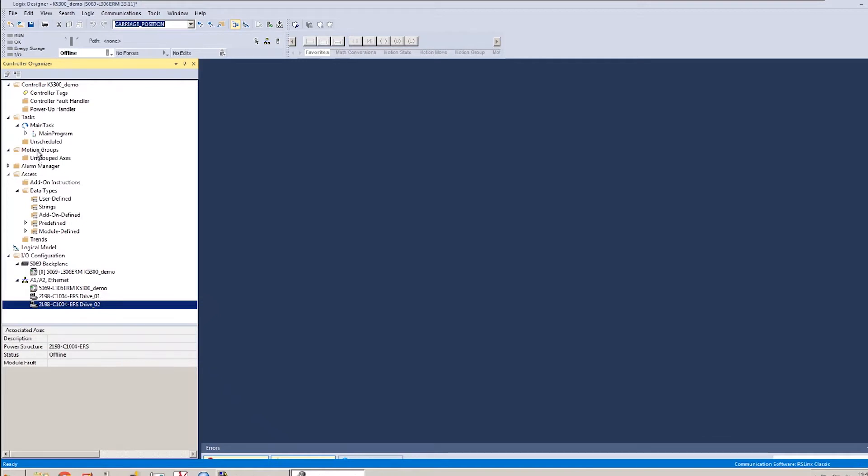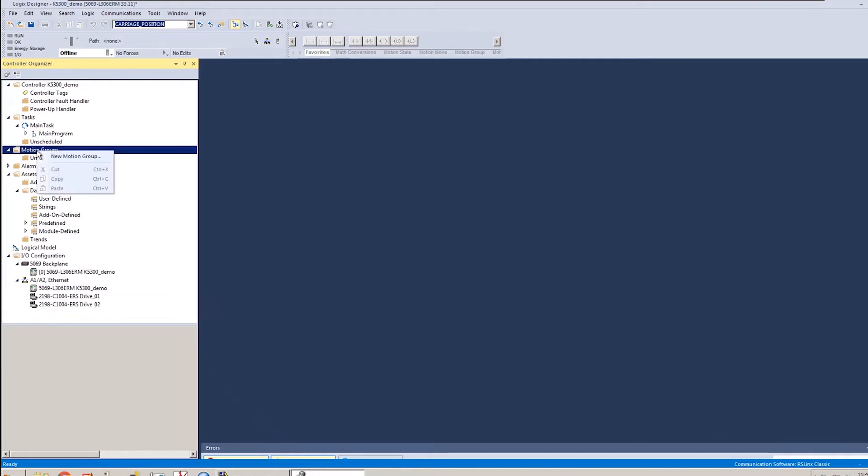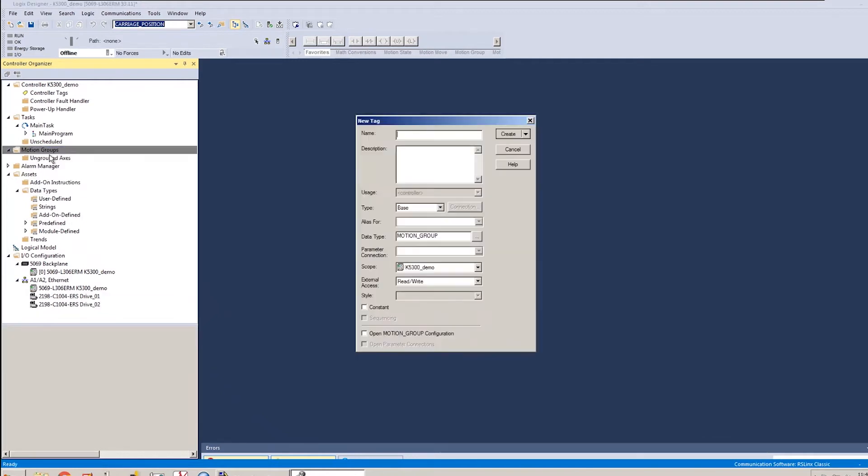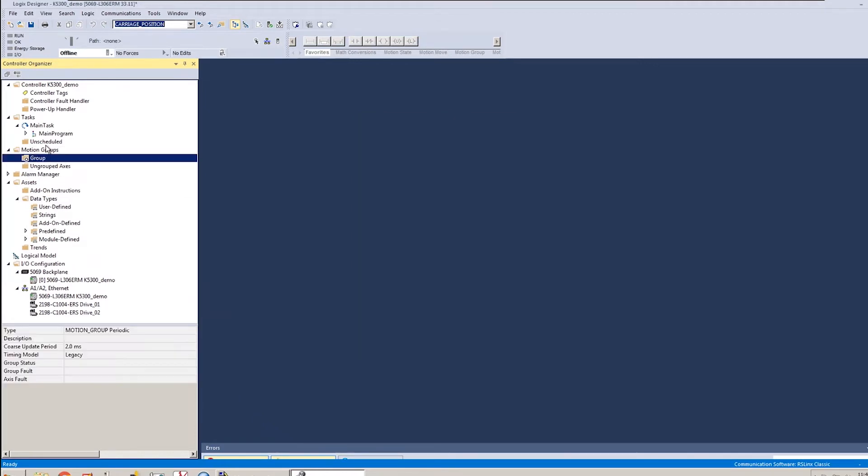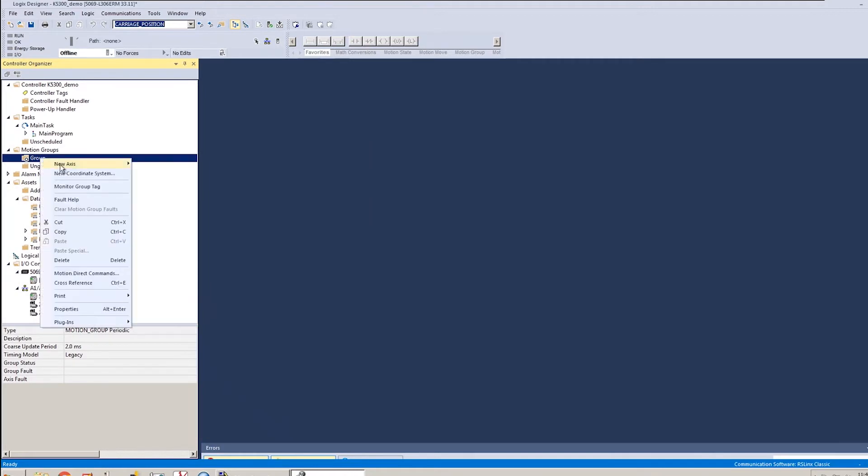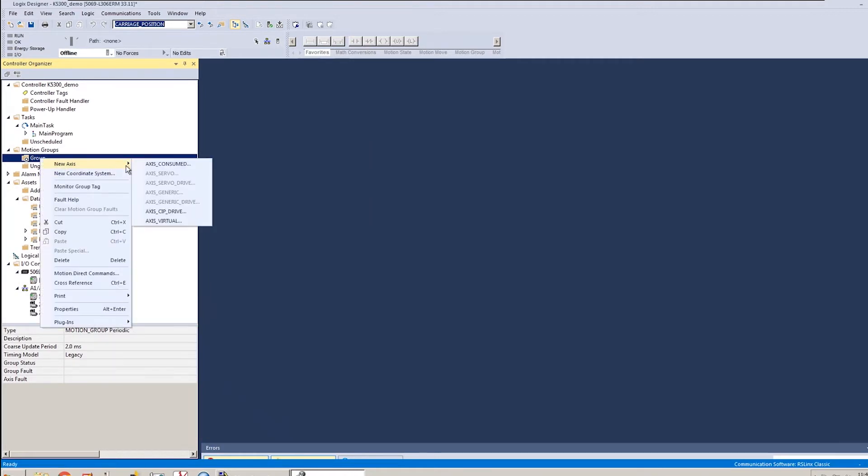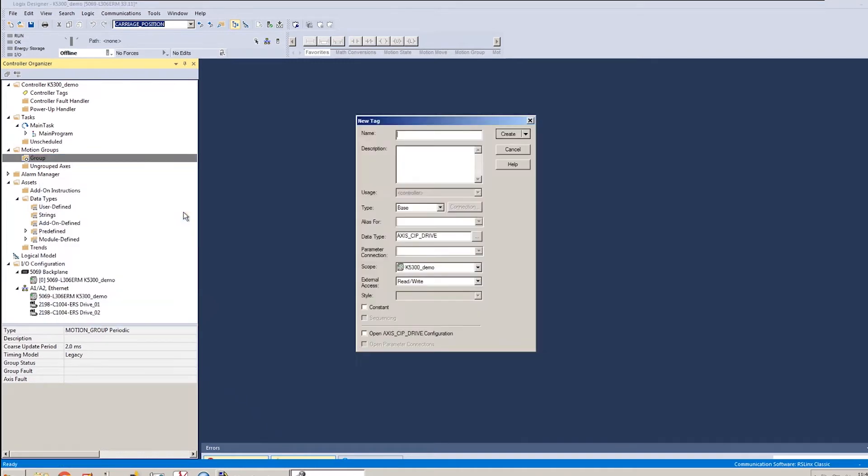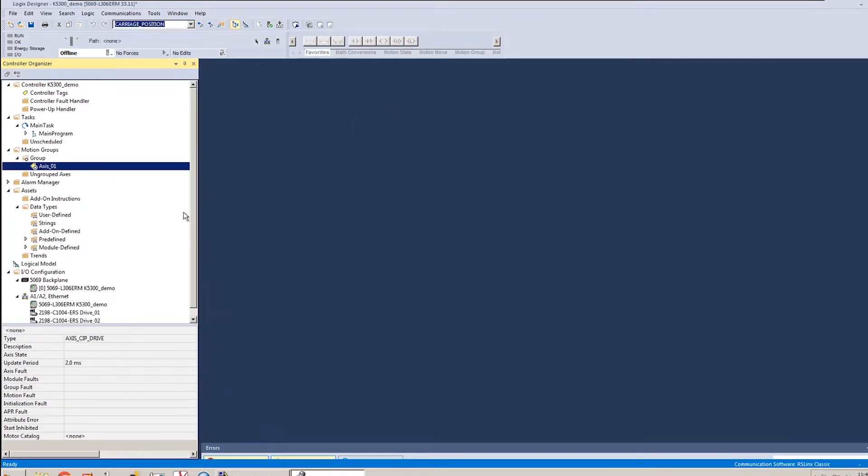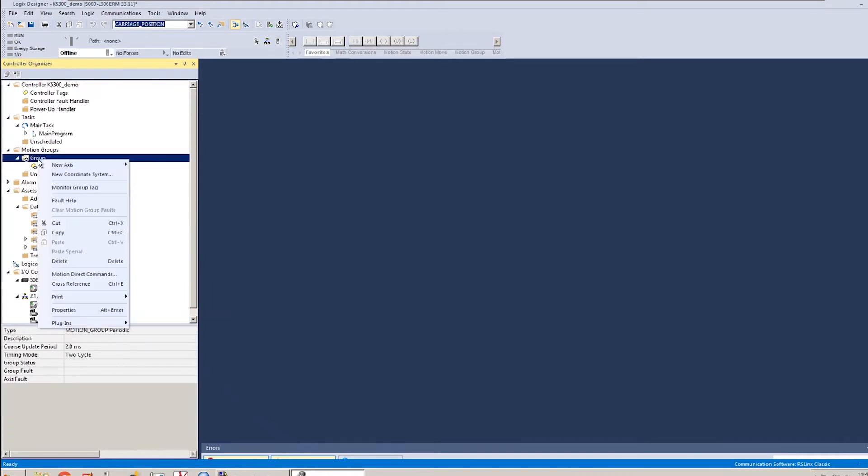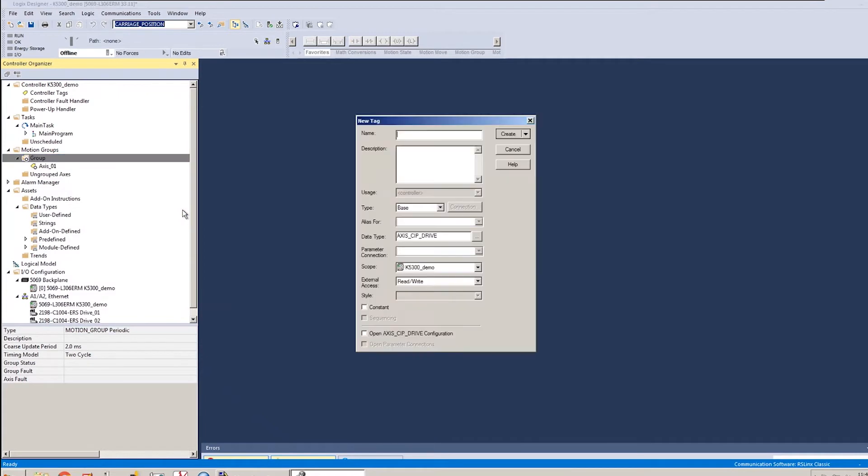The next thing I'm going to do is create my motion group and add my axes into my motion group. So there's my group. I'm going to create my first axis, and for all the Ethernet drives, you always use axis CIP drive as your axis type. So I'll call this axis one to match my drive one. And I'll do the same thing and make an axis two to match my drive two.